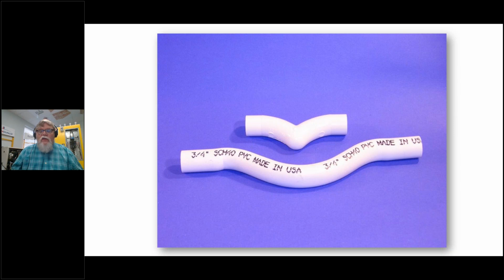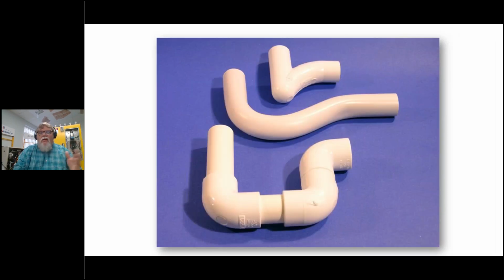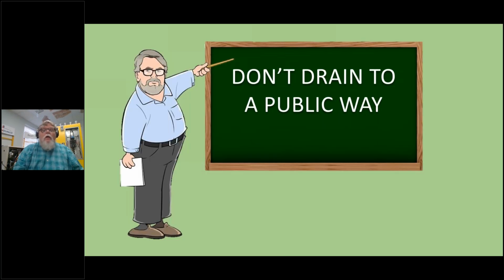I may not know exactly what's going on with it, but I do look for stains, indications that maybe the system has overflowed at some point. I look in the wintertime, especially, when we're kind of at a loss about some of the things we're going to inspect on the HVAC system. I look all around the unit. Do I see water stains? If I see water stains, I make sure I point that out. And I may even give them a note, because I am a licensed HVAC contractor. I say it may have something to do with your trapping, have somebody come out and check it. But if I see P-traps, generally I'm not overly concerned. I figure they can probably operate well.